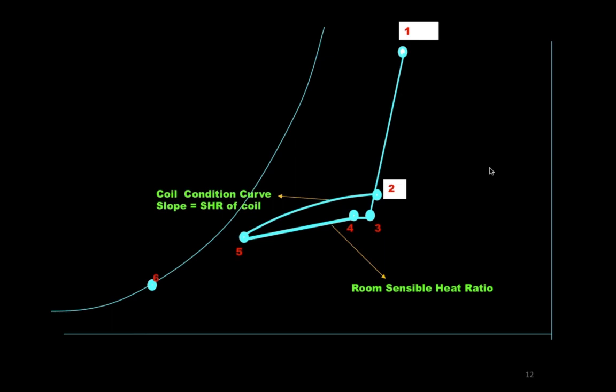Because of the nature of design, the way coils are selected, the way they are installed in the air handling unit, and the way we operate it, the coil tends to become too big, even at the starting point of the cooling coil operation. Let me continue to elaborate this through a psychrometric representation. Here it is. We have the space that we need to maintain at condition 4, maybe 24 degrees Celsius thereabouts. And this is the return air condition in the air handling unit.